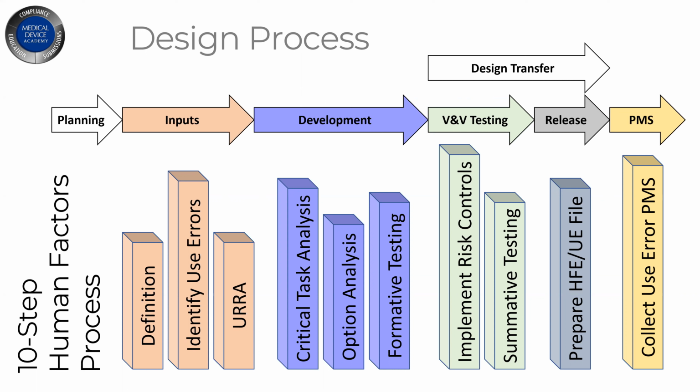For the design input stage, you want to define your usability user interface issues. You want to identify any use errors, and you want to perform your use-related risk analysis. It's very similar to performing a hazard analysis.